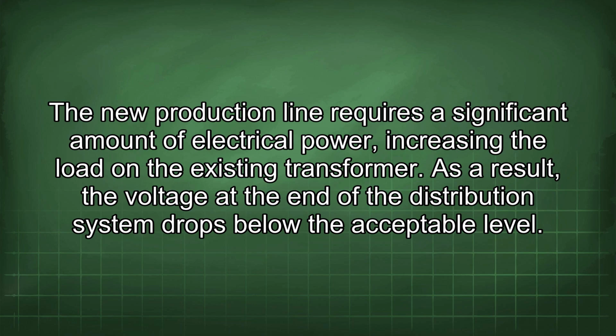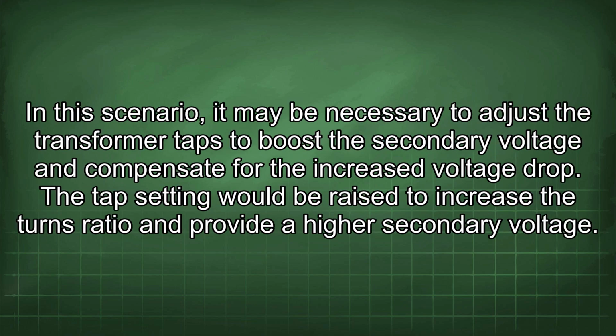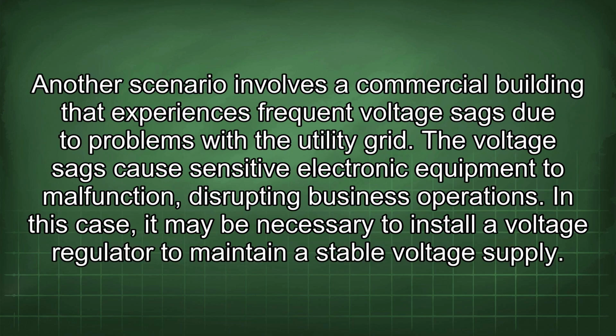As a result, the voltage at the end of the distribution system drops below the acceptable level. In this scenario, it may be necessary to adjust the transformer taps to boost the secondary voltage and compensate for the increased voltage drop. The tap setting would be raised to increase the turns ratio and provide a higher secondary voltage. Another scenario involves a commercial building that experiences frequent voltage sags due to problems with the utility grid.